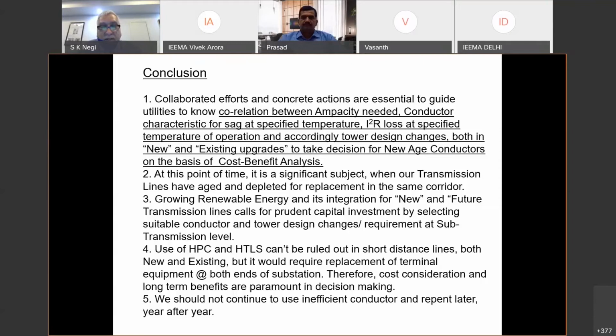The other day the Prime Minister made an announcement that 30,000 megawatt of renewable energy will come in the Kutch area. It will be both hybrid, I mean solar and wind put together. So we will have to integrate this energy from the sub-transmission network to the main transmission network and then carry it to other states. So it is very, very important that the right conductor is selected, and with a minimum of transmission lines, maybe we can bypass the N-1 criteria. Of course, it is a decision making, and this renewable energy particularly calls for the use of these new age conductors.